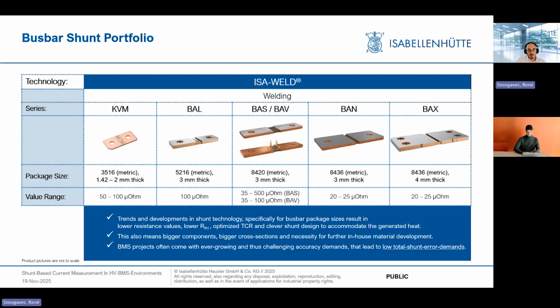So we did have a 5 micro ohm BAS shunt, but it got discontinued because we only had few inquiries coming from this variant. It has a very low voltage drop and is only feasible if you have 2,000 to 3,000 amps, which not many engineers really like to work with, to amplify that high because of the noise that might come out of it. Similar for the 500 micro ohm BAS in the middle that you see. The voltage drop is compelling and high, but if there's a need for such a value, most customers try to design in an SMD shunt, seeing their capabilities nowadays, because in our portfolio we have an SMD shunt going down to 100 micro ohm.